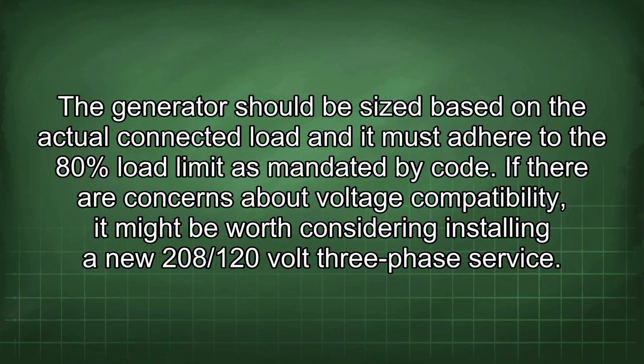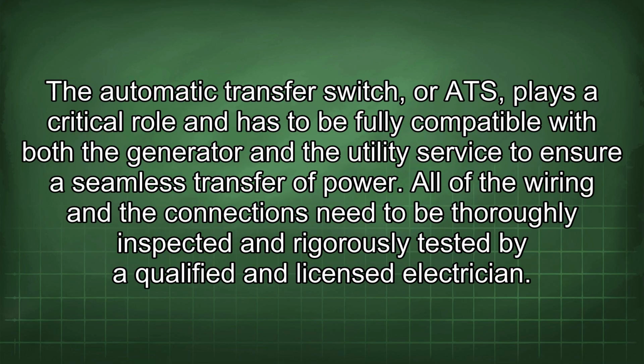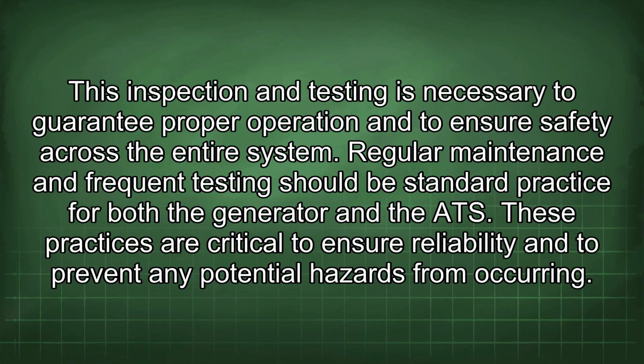208/120 volt three-phase service. The automatic transfer switch, or ATS, plays a critical role and has to be fully compatible with both the generator and the utility service to ensure a seamless transfer of power. All of the wiring and the connections need to be thoroughly inspected and rigorously tested by a qualified and licensed electrician. This inspection and testing is necessary to guarantee proper operation and to ensure safety across the entire system.